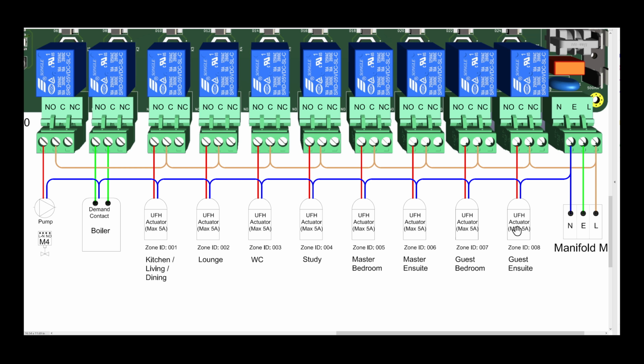If it's wet underfloor heating, so it's only simply an actuator, then it connects directly. If it's electric underfloor heating under 5 amp, it can connect directly. If it's electric heating over 5 amp, then the relay should only power a contactor, and the contactor should power the electric underfloor heating.